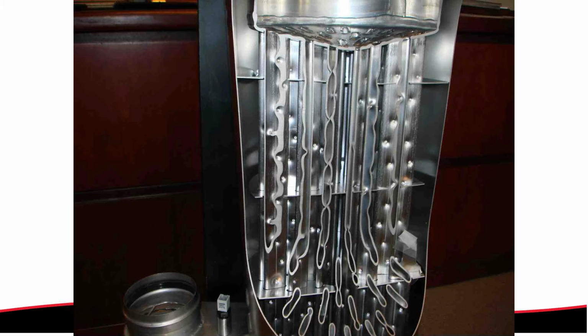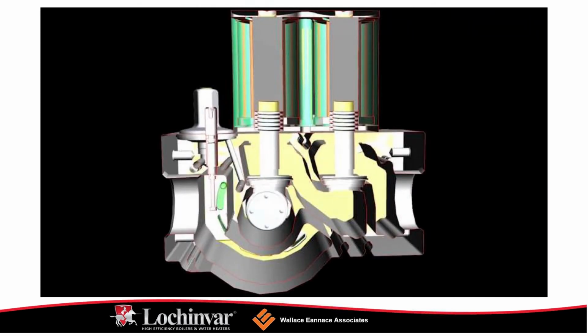So the combustion system inside the Knight and the Noble here actually is metal fiber material. This is a 360-degree design, as you can see by the photo. Direct spark ignition and a 5-to-1 turn down ratio.